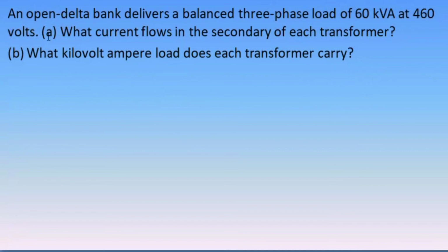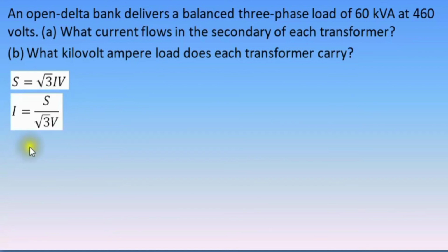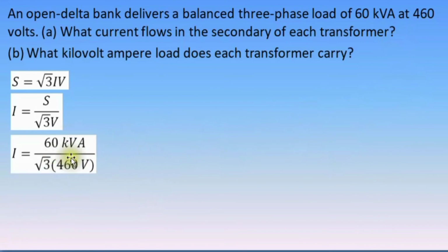For letter A, let's determine the secondary current of each transformer. From the formula of the apparent power in a three-phase system, that is square root of 3 times current times voltage, cross multiply square root of 3 and voltage to the other side of the equation, we have current is equal to the apparent power divided by square root of 3 and divided also by the voltage. Substitute the given values. We have 60 kVA divided by square root of 3 and 460 volts, that is 75.307 amperes. So this is the current that flows in the secondary of each transformer.